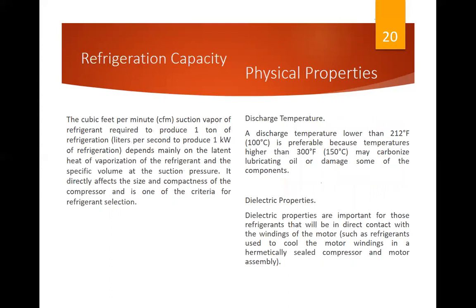Refrigerating capacity. The cubic feet per minute (CFM) of suction vapor of refrigerant required to produce 1 ton of refrigeration, or liters per second to produce 1 kilowatt of refrigeration, depends mainly on the latent heat of vaporization of the refrigerant and the specific volume at the suction pressure. It directly affects the size and compactness of the compressor and is one of the criteria for refrigerant selection.